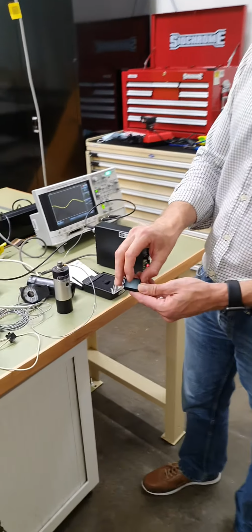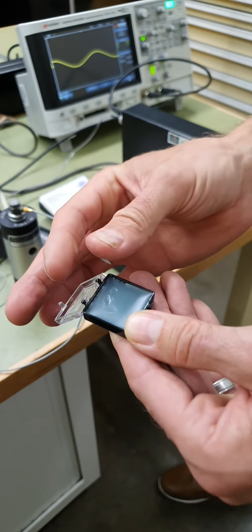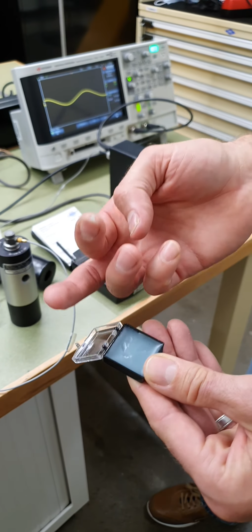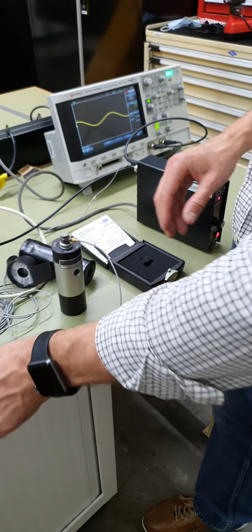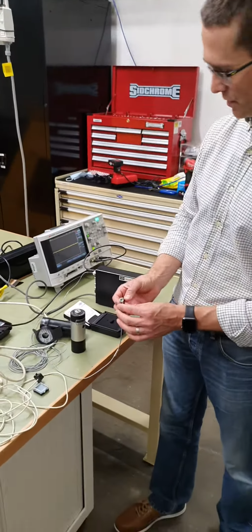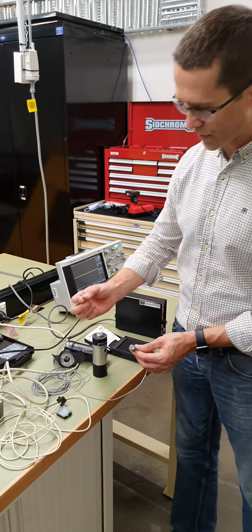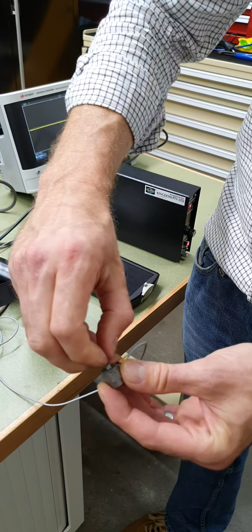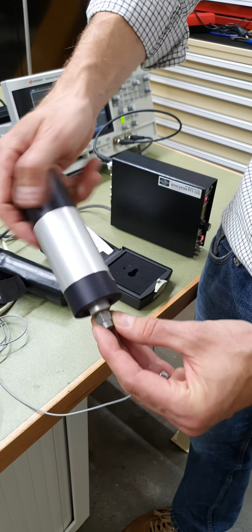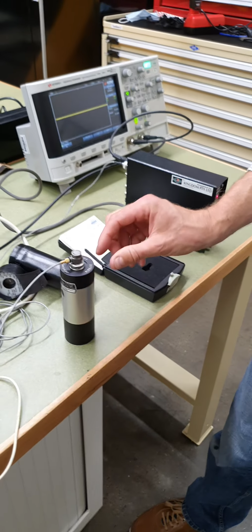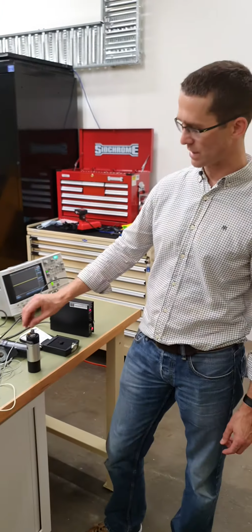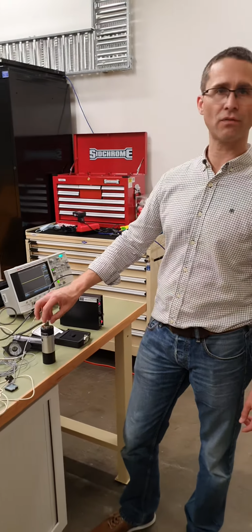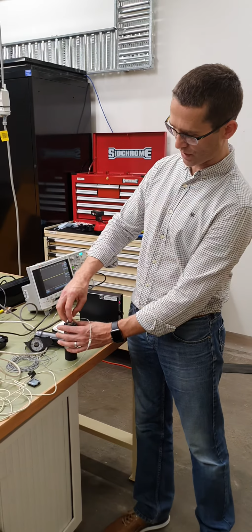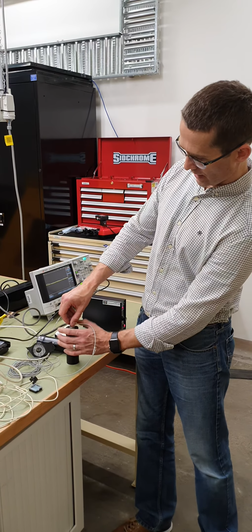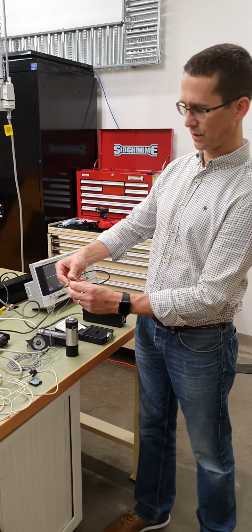We use beeswax quite often to attach these devices to our structure. This is synthetic beeswax, so we only really need a very small amount of this. You essentially want a very thin film of beeswax, so you can see that I've attached that to the calibrator with beeswax. Sometimes we also use a stud mount, so here's a very small stud that's threaded on both ends. We can screw that into the transducer like this, and then into the accelerometer calibrator like this, or we could drill and tap our sample, or we could put a magnetic mount on our sample if it was metallic, and we can use all manner of different types of attachment, but the attachments should be suitable for the type of measurement. Beeswax is less stiff, let's say, than a physical stud mount.